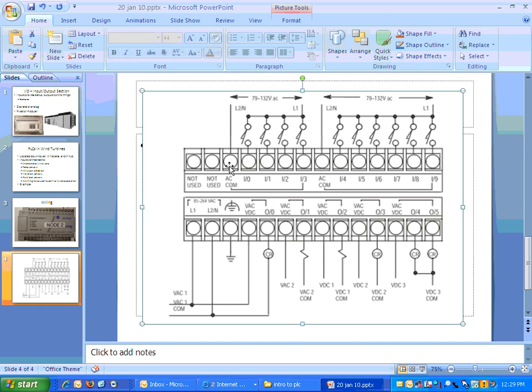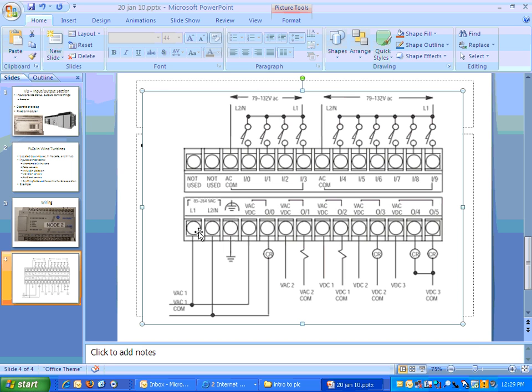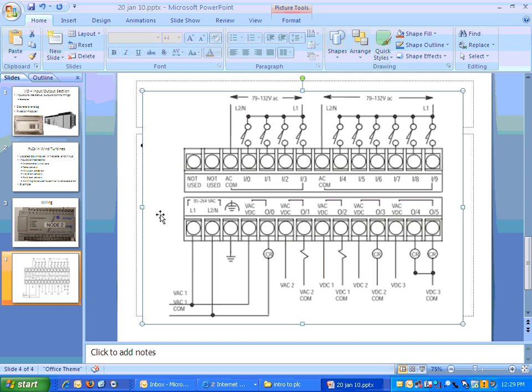Okay, so to wire this up, there's two parts to the operation. And we may do this in class if we have enough time. The first part is you have to connect power to it. And it's powered by, well, it can go anywhere from, oh, let's just say 85 to 204, 264. We use normal 110 volts AC. So L1 goes to the hot and L2 is going to be tied to the neutral. You would also connect to ground if you were installing it. For what we're doing in the lab, I don't think we need a ground. If we wire these up in the computer lab, I may just do that with power cables. Then you could hook up all three. The L1 will be black, the L2 will be white, and the ground will be, normally it's green.